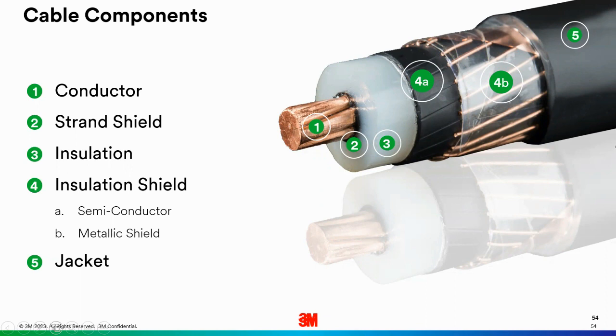And then just moving along, the insulation shield, basically made up of your semicon and your metallic shield, whether that's neutral wires or tape shield. But those two components make up the insulation shield. And then of course you have your outer jacket. So that's just the basic construction of a cable.